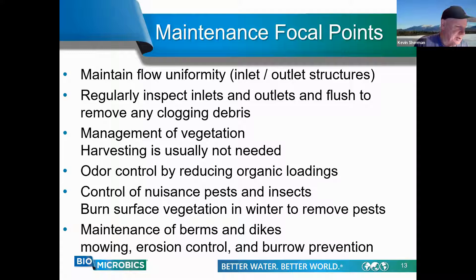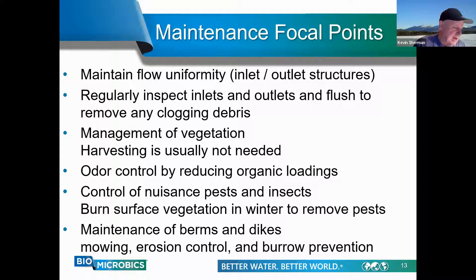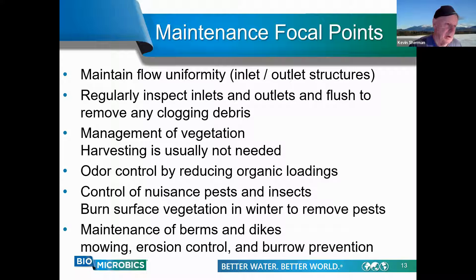Additional maintenance issues may come up as the constructed wetland ages. A key consideration is ensuring there is no short-circuiting in the effluent flow — if the effluent arrives too quickly at the outlet, it will have an unacceptable level of BOD and TSS remaining. Pests and insects can be controlled by burning the surface vegetation during the winter. These wetlands may attract burrowing animals, which you'll want to discourage before they ruin the liner containment. Maintenance is pretty self-evident and easy, requiring no esoteric machinery — basically furrows, hose, and shovels.